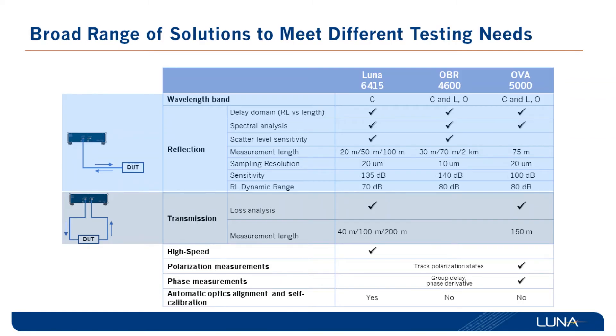Here we have a quick comparison summary of the three solutions for characterizing photonics integrated circuits: the Luna 6415, OBR 4600, and the OVA 5000. None of these instruments need to be sent back to the factory for calibration — everything can be done on site by the user. One exception is the Luna 6415, which has automatic optics alignment and self-calibration functions, so once you turn on the instrument it will go through those cycles quickly and be ready for taking measurements.